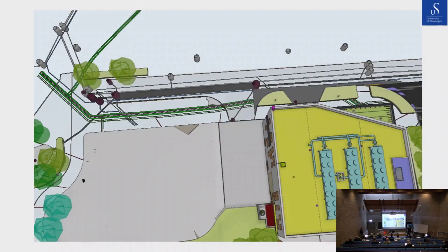Here you see the roof. Here you see the coolers that we use to reject or extract heat from the air. I'm working on calculations, but my current calculations say that we can utilize almost 3 million kilowatt hours from the air. If you compare that to what you would have gotten from a PV system on the same space on the roof, on 100, 200 square meters, that's quite a lot more. So utilization of air combined with the boreholes here in Stavanger is an interesting concept that we hope will provide a nice energy balance.